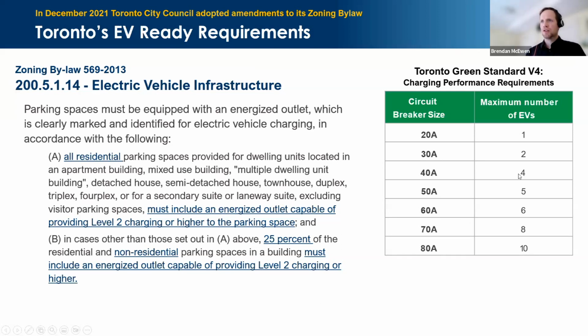There are charging performance requirements that limit how much load sharing you can do on a branch circuit or branch panel, limiting you to 4-share on 40 amp circuits. Previously it had been 3-share, and then we did some analysis looking at how far people tend to drive in the Greater Toronto Hamilton area and Toronto. It's reasonable to have 4-share on 40 amp, or you could do things differently, perhaps up to 10-share on 80 amp circuits.